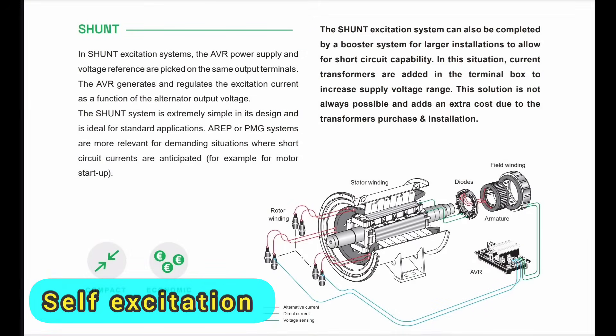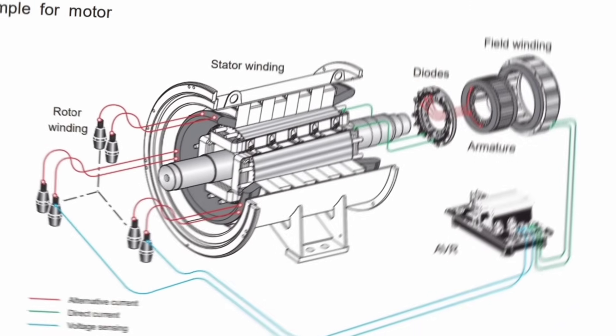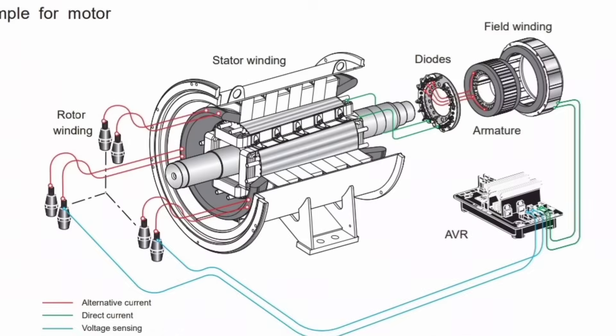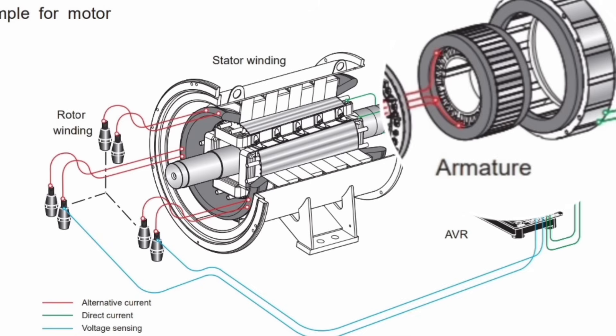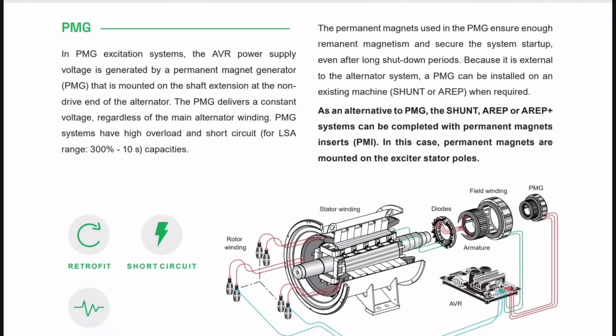The first type is the self-excitation system. In this system, the alternator takes its own voltage from the main stator winding as a sensing supply. The AVR, automatic voltage regulator, converts this AC voltage into DC and sends it to the rotor winding through rectifiers. But this system has one big drawback: it depends on residual magnetism to generate the initial voltage. If the alternator stays off for a long time or if there's zero residual magnetism, the alternator will not start generating power.